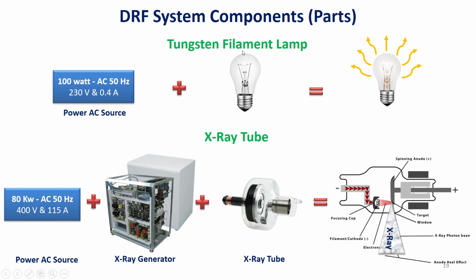In the past, most people used tungsten lamps to illuminate or light their house. In this slide, we see an example of a 100 watt tungsten filament lamp. We need an alternating source, an AC source, to generate light using such lamps. In Lebanon, such sources come with a 230 volt operating voltage and 50 Hz operating frequency, and the current consumption is around 0.4 amp for each 100 watt lamp. In the case of the DRF system, in order to generate an X-ray, we need an X-ray tube instead of the lamp and an 80 kilowatt X-ray generator, as well as a hospital 80 kilowatt UPS power source.